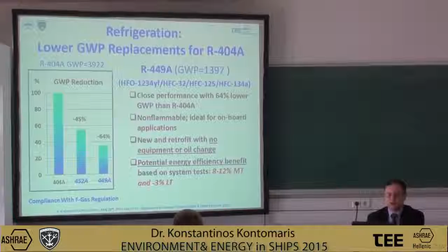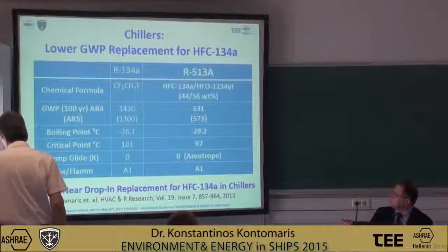All right, so moving to the air conditioning or chiller application, HFC 134A is the refrigerant of choice today that is used predominantly for, certainly for marine chillers. A new fluid has been registered with ASHRAE Committee 34, 513A. This is also a fluid that is based on hydrofluoroolefin 1234YF. It's a blend of this low GWP fluid with 134A, and achieves a GWP of 631, which is about 56% lower GWP than the current fluid, 134A. So again, it's a major step in the right direction of reducing GWP.